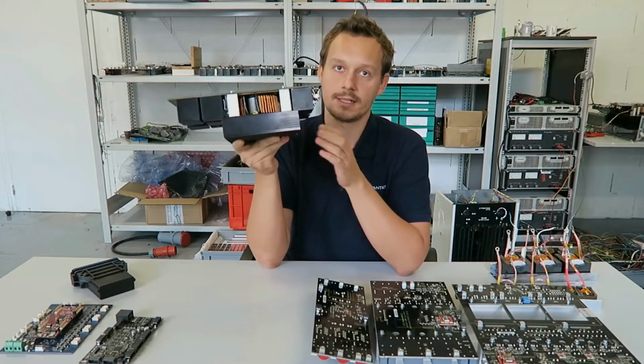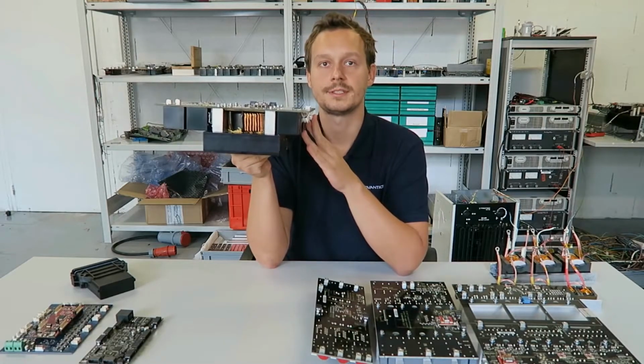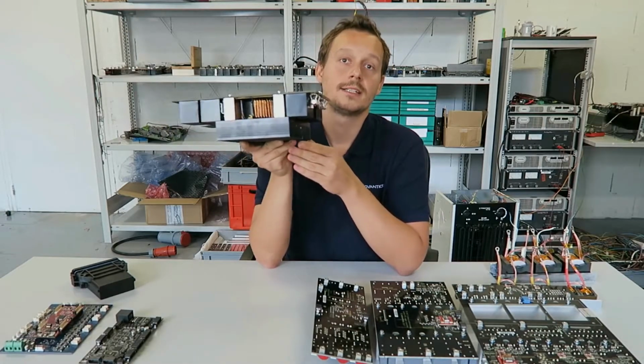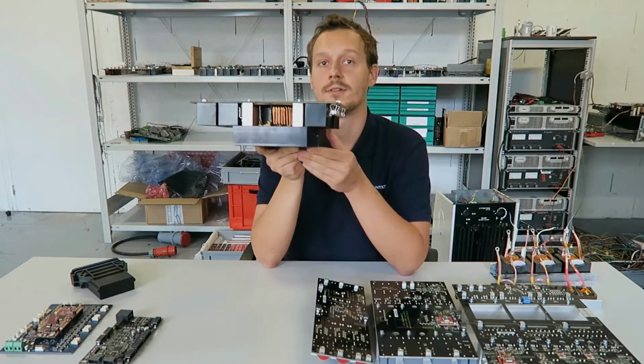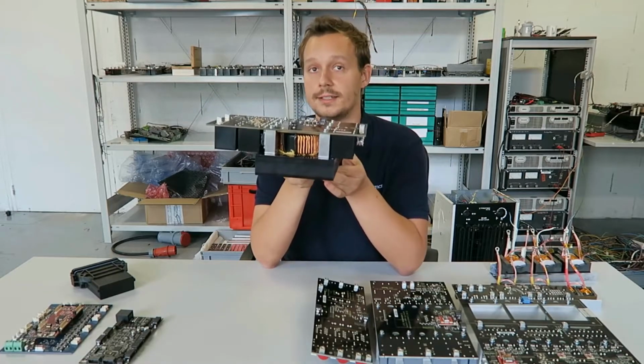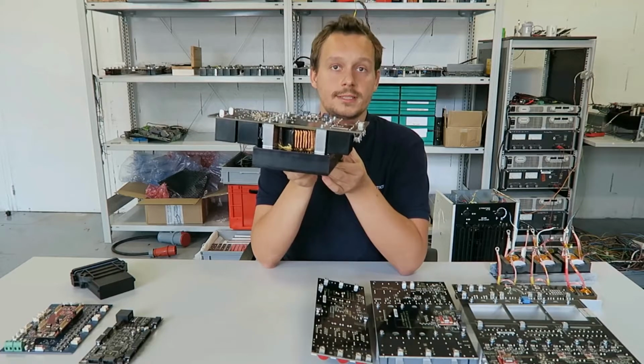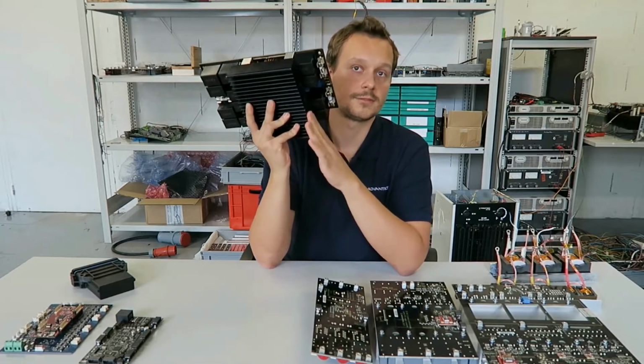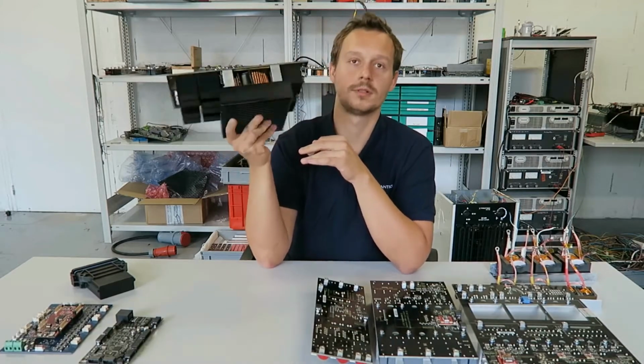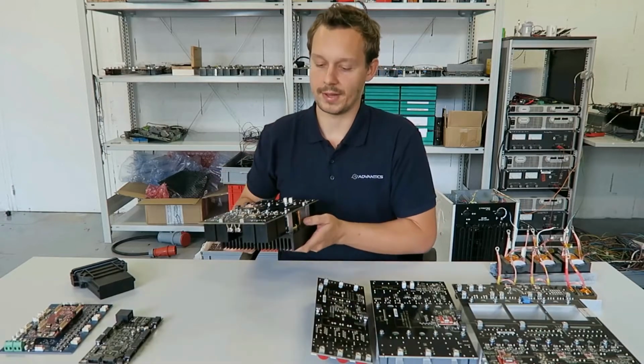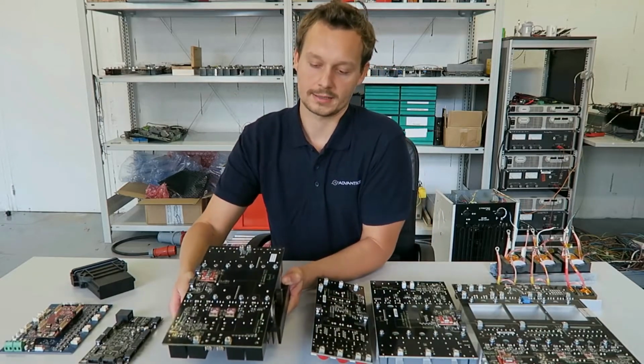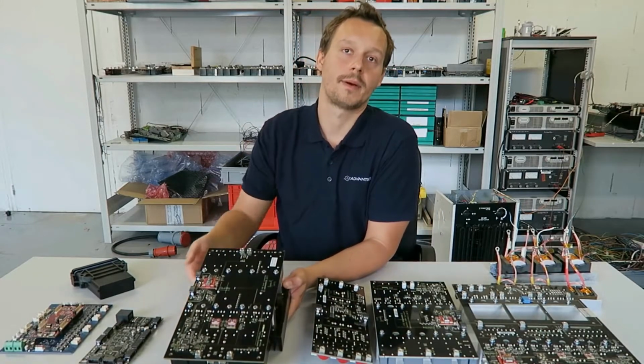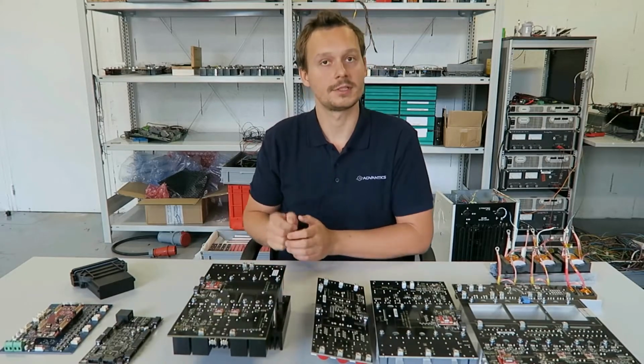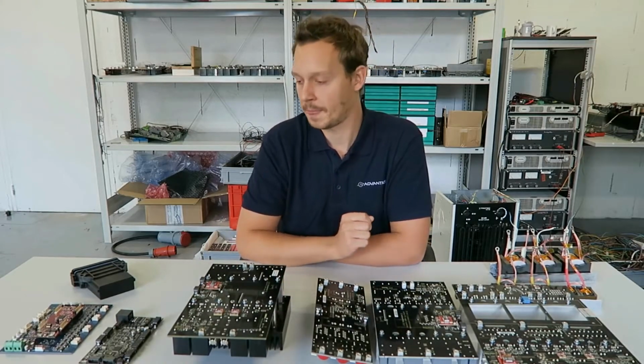This is 25 kilowatt with 99% efficiency. That means at 25 kilowatts you would have only 250 watt losses, which this heatsink is for. So it's pretty small, and that really makes it possible to pack a lot of power in one package, for example if you have the units in parallel.